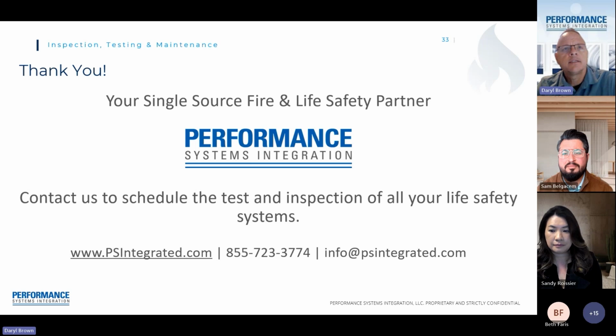Another question was, can you test your fire system? As Sandy had stated before, the state of California and other jurisdictions, whether the Northwest or California, require specific licensing for a fire sprinkler technician and a fire alarm technician. For the state of California, for a vendor to do testing on a fire alarm system, the contractor's license is a C10. For testing on a fire sprinkler system, the license requirement is C16. The state of California also has some specific requirements for an electrical technician, which would be fire alarm, and for a sprinkler technician as well, similar to the fire alarm technician.